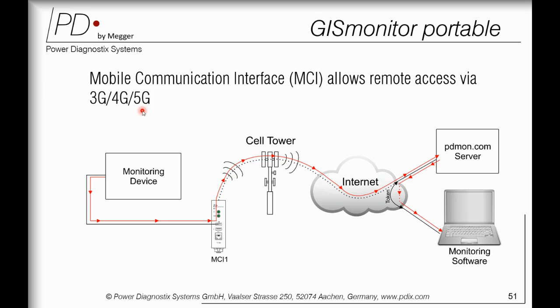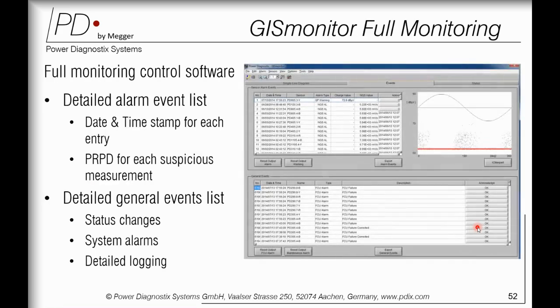Along with this, we also have the MCI, the mobile communication interface, which allows remote access via different cellular networks like 3G, 4G, or 5G. You have the monitoring device here, and this monitoring device is connected with the MCI, and the MCI has internet, which is connected with the cloud or the server, and you can have live monitoring, live observation, and live measurement on your PD monitoring device. It also captures all the features like alarm events and general events, along with the date and time of the PRPD pattern, and also the details.